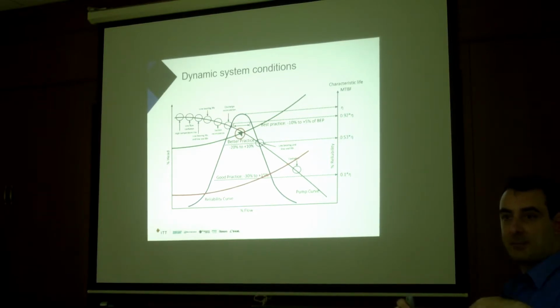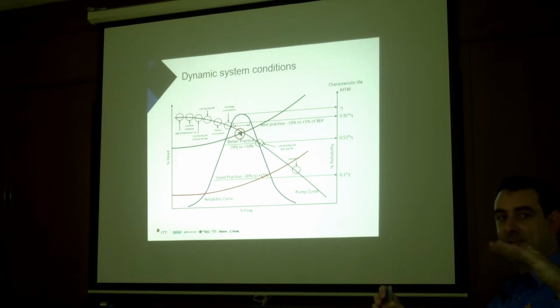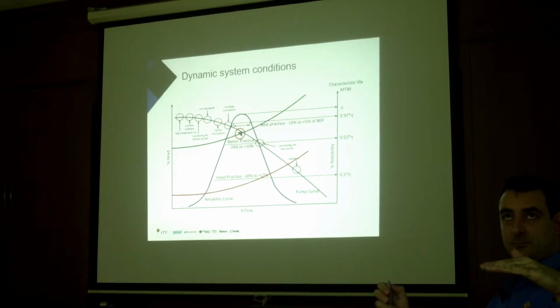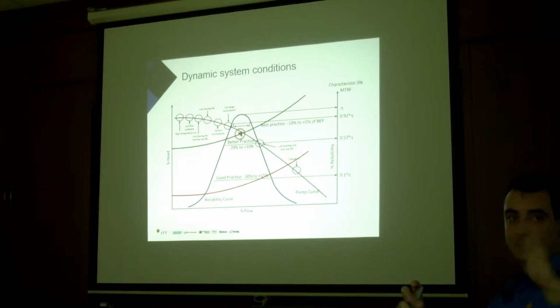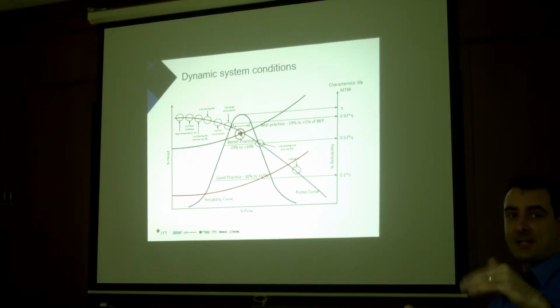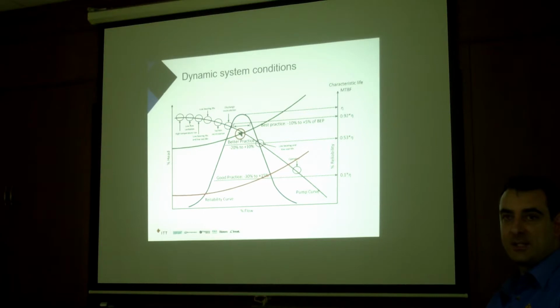So we need to know what product's being pumped, so we can amend, change our calculations. So that means this Pump Smart, if in a terminal with a batch controller controlling into the low flow, will decrease the speed together, right? If it's a tank terminal where there's a batch controller for truck loading, yeah, then actually the system curve is usually pretty good. We would consider it as almost a flat curve because the batch controller throttles the flow. So you've got fixed flows. But the speed in that case will change up and down based on the supply tank level, automatically. So that one's very easy.